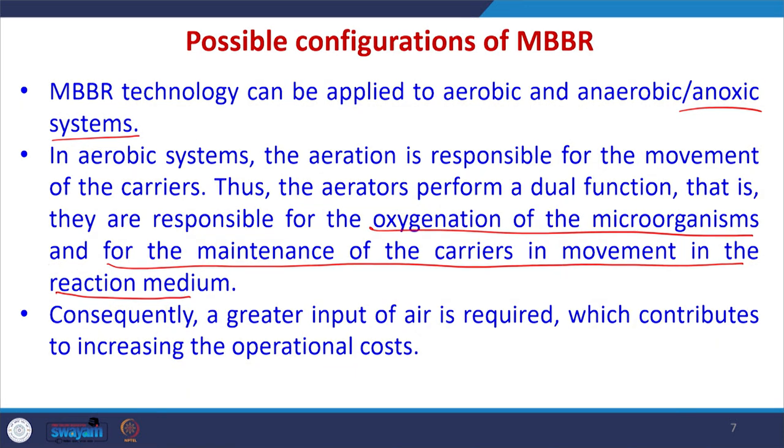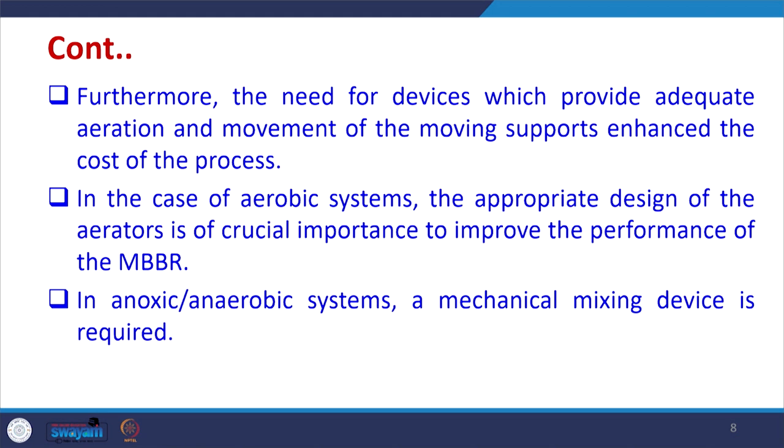For the aeration system, MBBR is very demanding. Consequently, a greater input of air is required, which contributes to increasing the operational cost in the MBBR as compared to a traditional activated sludge system, since we have to move the moving bed biofilm all inside the reactor. That means the air input has to be higher, then only the movement will happen. Furthermore, the need for devices which provide adequate aeration and movement of the moving support enhances the cost of the process.